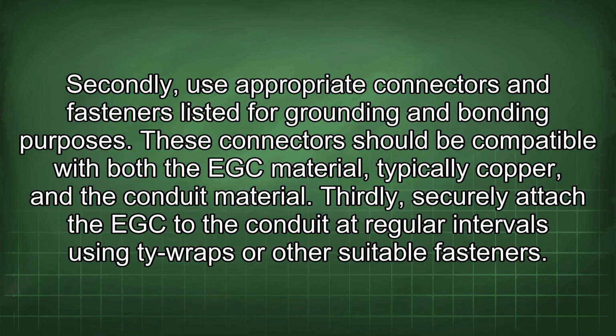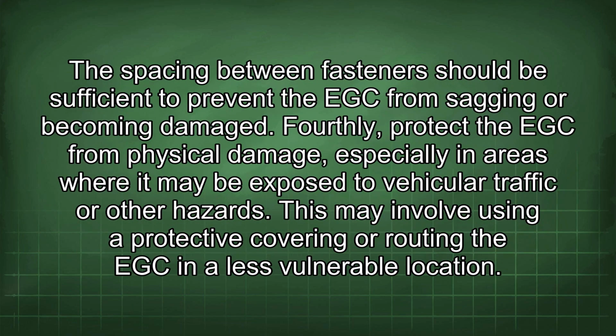Thirdly, securely attach the EGC to the conduit at regular intervals using tie wraps or other suitable fasteners. The spacing between fasteners should be sufficient to prevent the EGC from sagging or becoming damaged. Fourthly, protect the EGC from physical damage, especially in areas where it may be exposed to vehicular traffic or other hazards. This may involve using a protective covering or routing the EGC in a less vulnerable location.